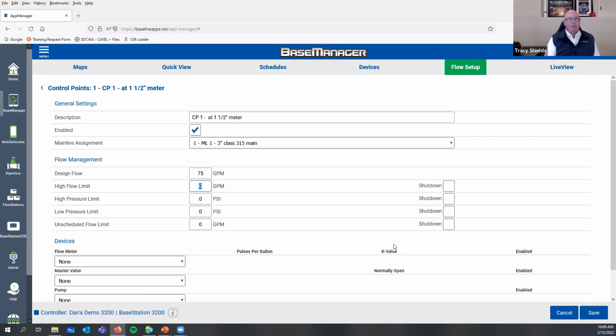Because their high flow limit may be set inaccurately - we see the flow live, we're not masking our flow with math, so we may be able to see zones opening and closing, and our high flows may spike a bit higher than we'd think on paper, hydraulically, as valves open and close. Yeah, that's interesting, I'd never even thought about that.